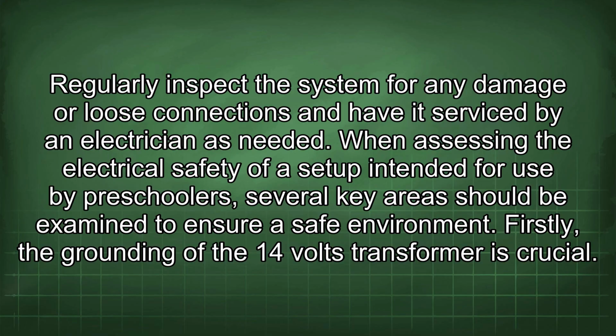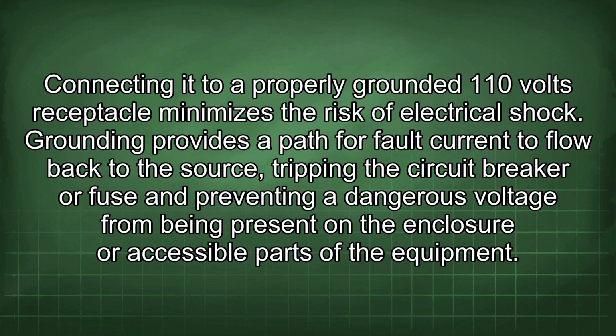When assessing the electrical safety of a setup intended for use by preschoolers, several key areas should be examined to ensure a safe environment. Firstly, the grounding of the 14 volts transformer is crucial. Connecting it to a properly grounded 110 volts receptacle minimizes the risk of electrical shock. Grounding provides a path for fault current to flow back to the source, tripping the circuit breaker or fuse and preventing a dangerous voltage from being present on the enclosure or accessible parts of the equipment.